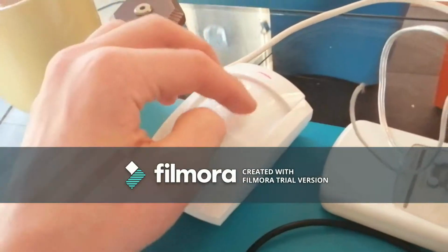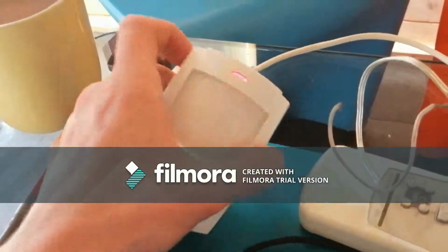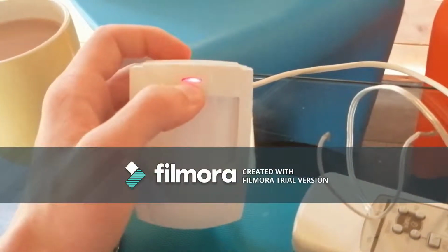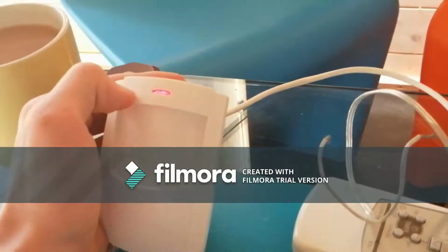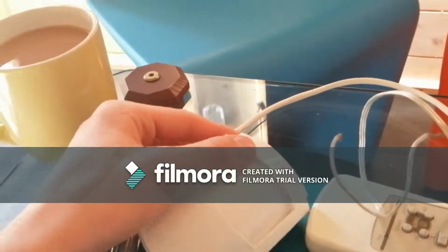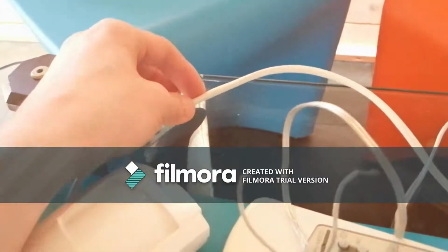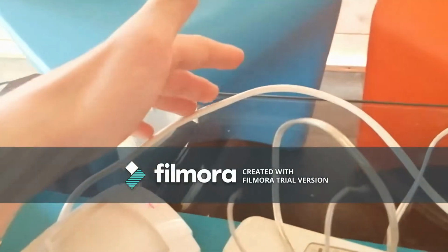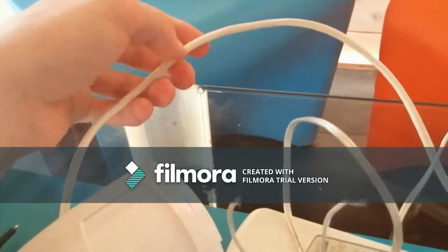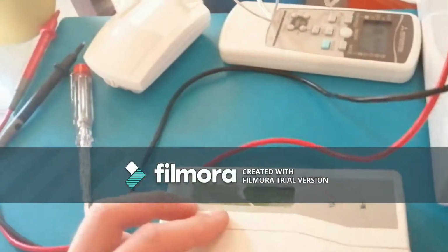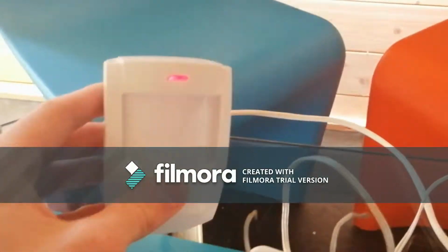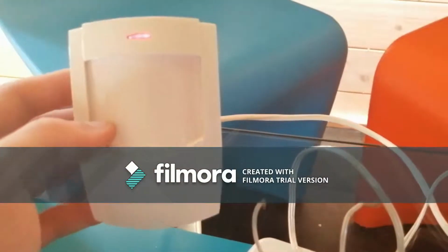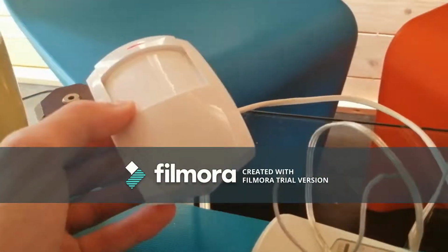Okay, if you walk into that area and the detector is illuminating, such as it is here, then you know it's not going to be a cable fault necessarily. It could still be, but it's likely that it isn't, because if it was, then you'd have a tamper condition. So once you've identified this sensor, how do you resolve the setting fault?